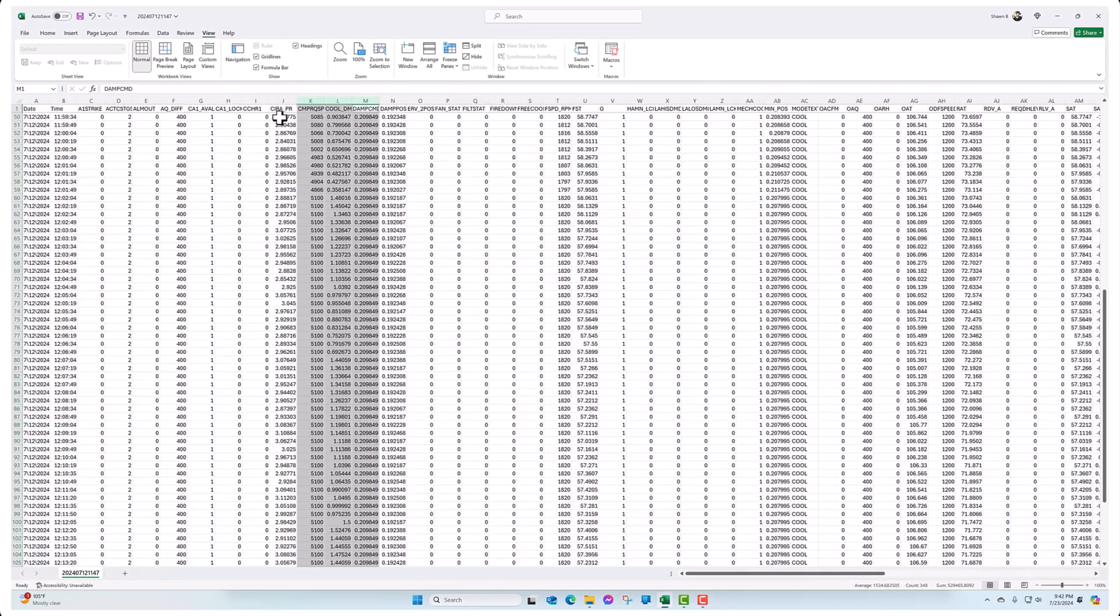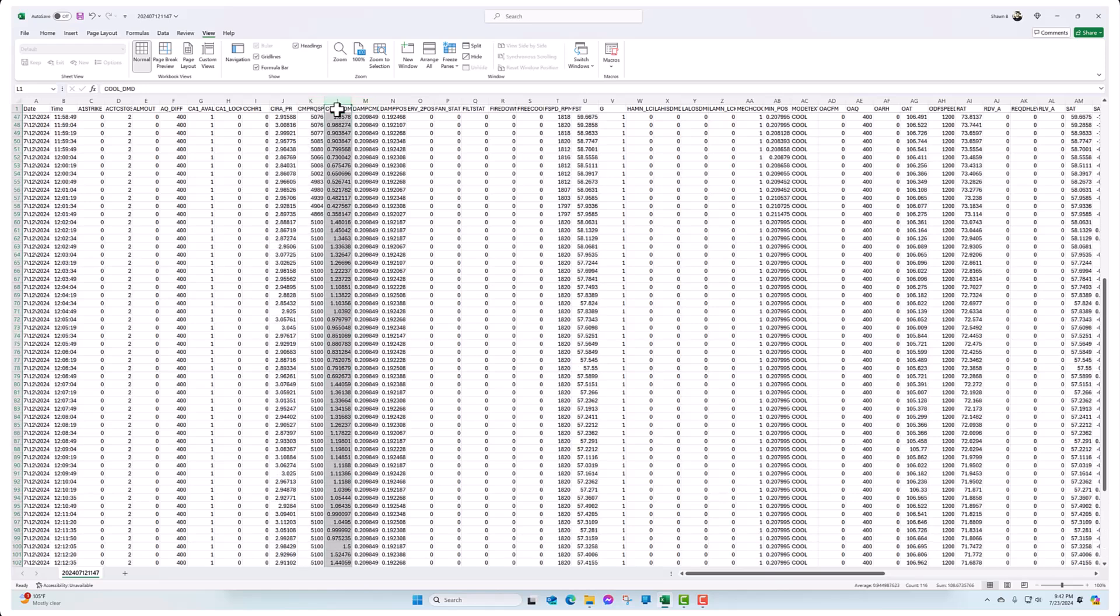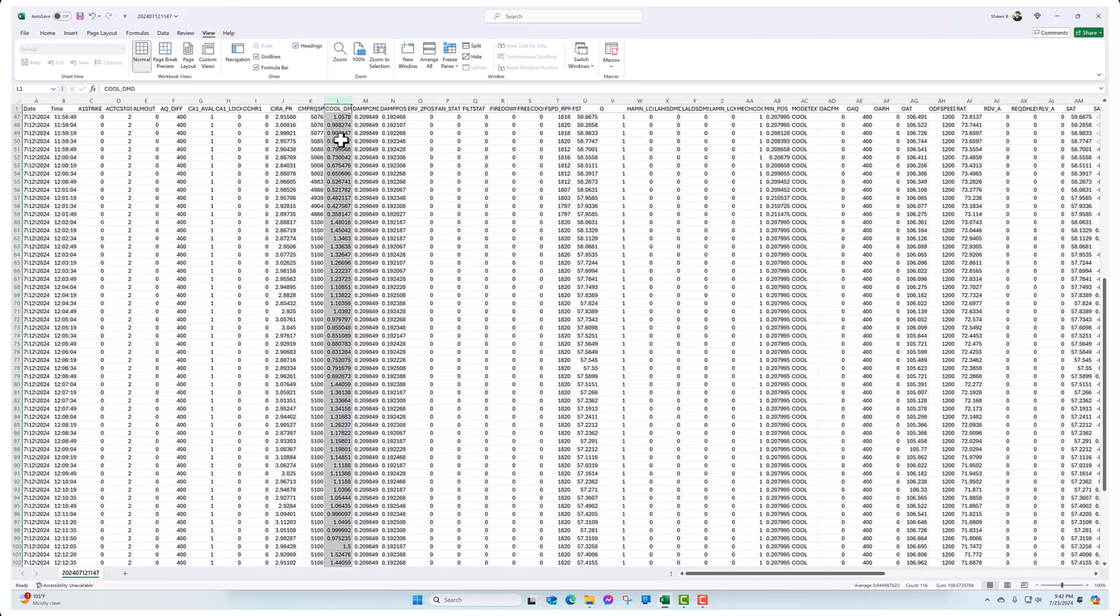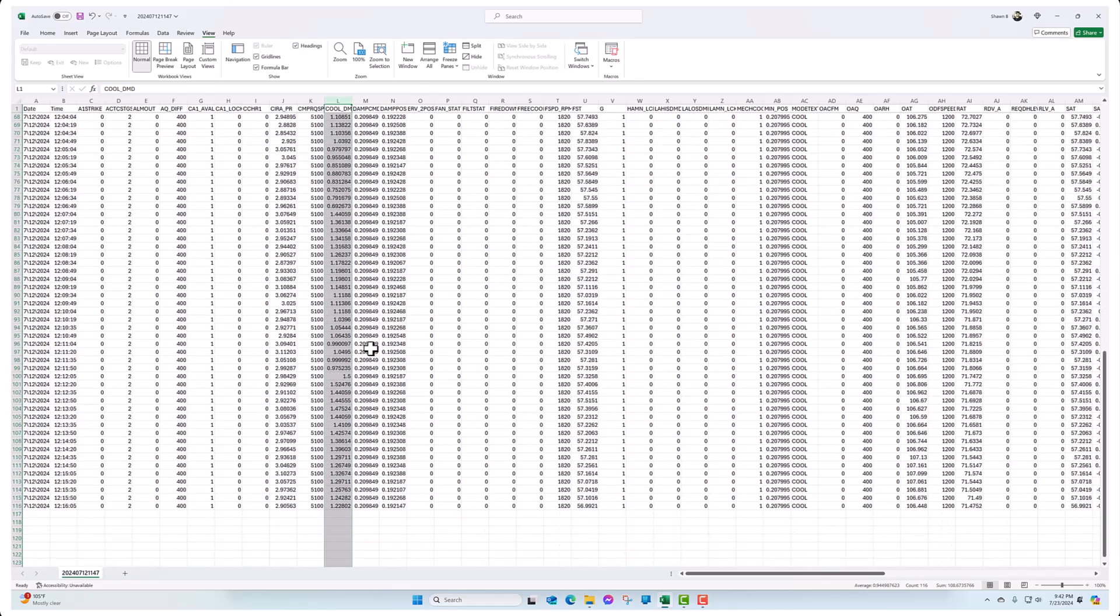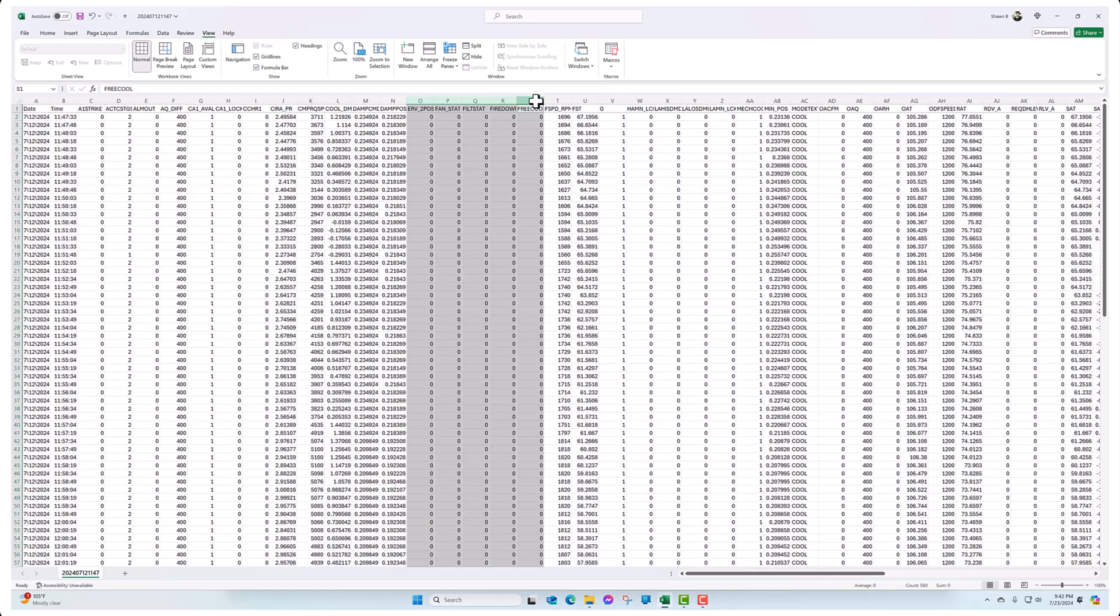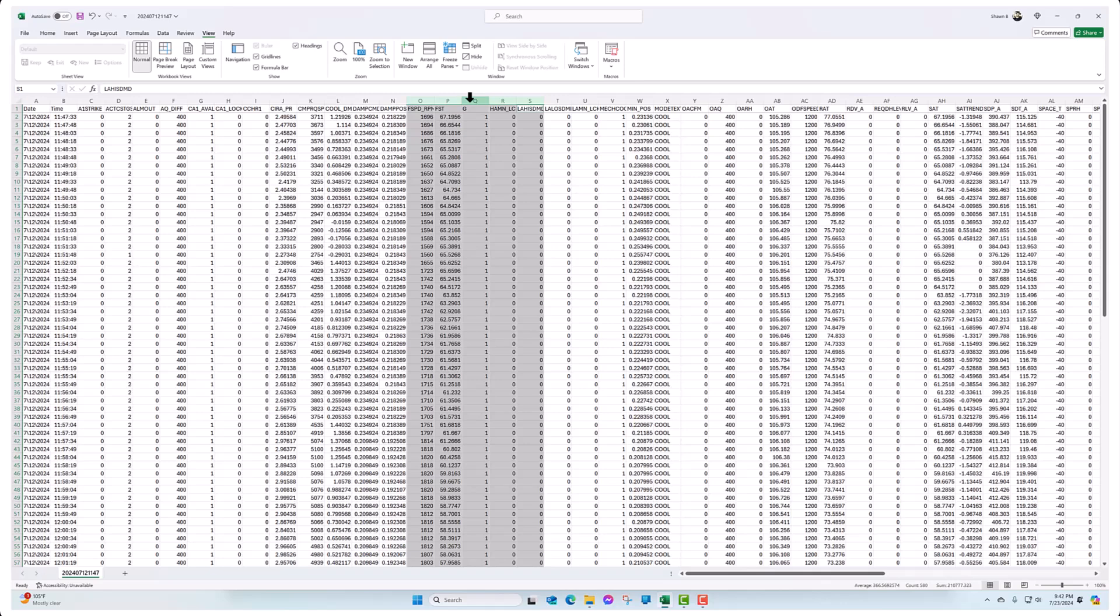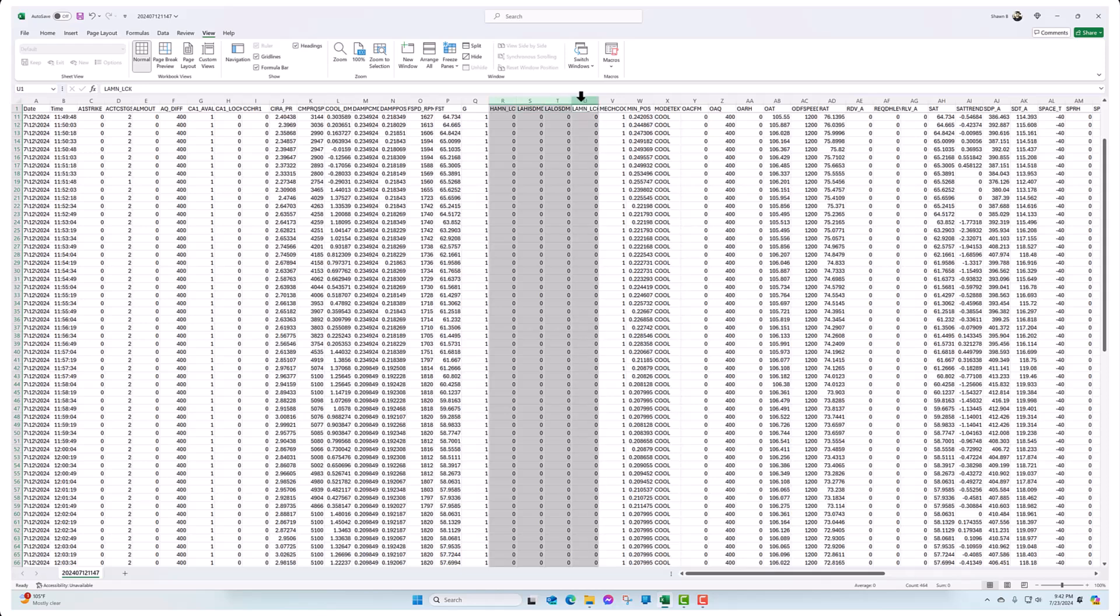We got our, here's the cooling demand. It's like a weird ratio here. You can see those and it starts going over one to one. I think these kind of can over speed and do a little more than their rated BTUs. Damper command. Damper position. That's from the feedback. You kind of see they're pretty matched there. ERV, fan stat, not using filter stat, not using fire shutdown. Those could be hooked up. Like I said, free cool. Let's go ahead and get rid of all that. Here's your G signal. Fan speed signal.